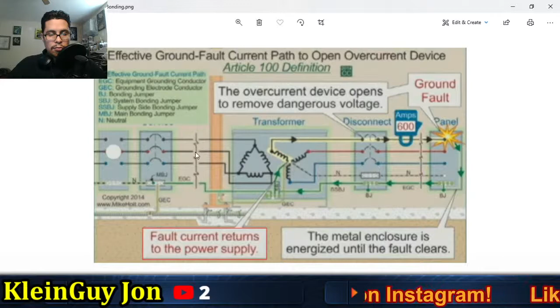Let's say now you don't have a grounding conductor bonded to the neutral, and instead you have a bonding jumper, so your equipment grounding conductor is only tied in and bonded to the metal frame, and you have a bonding jumper, and your equipment grounding conductor is also bonded to the metal of the panel, and not bonded to the neutral. What's going to happen? You're going to have voltage go straight to the earth. And like I said before, if someone's standing here and they touch metal, what happens? Boom, that's it. They're done. They're dead. Because now you've got all this metal bonded.